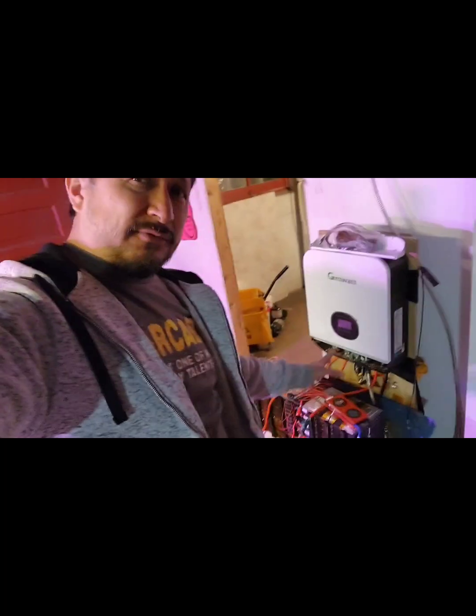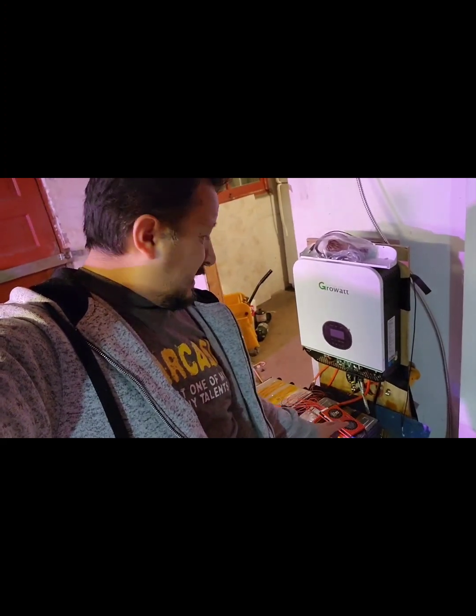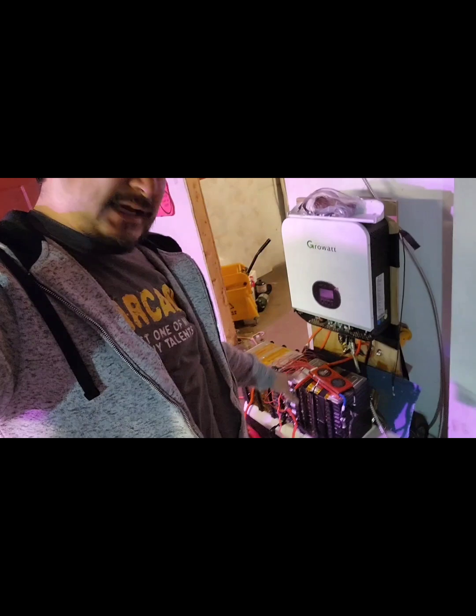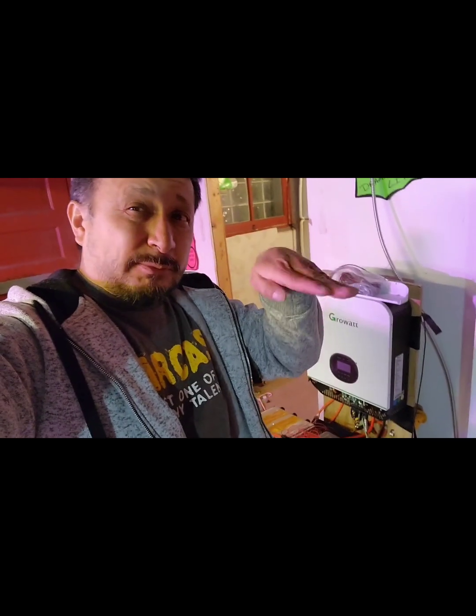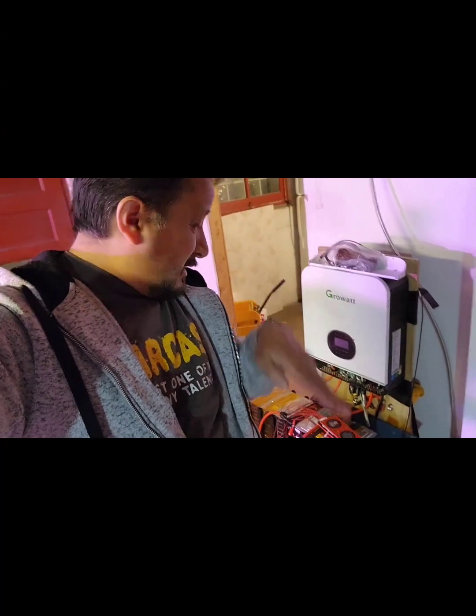There's 14 batteries right here, and it goes into the positive out. It starts with the negative of the bottom one and goes up to all 14, connecting into each individual battery. These are lithium ion batteries, so it monitors them so they don't go over 4.2 volts or below 3.2 volts, and it's supposed to keep them balanced within a certain tolerance.